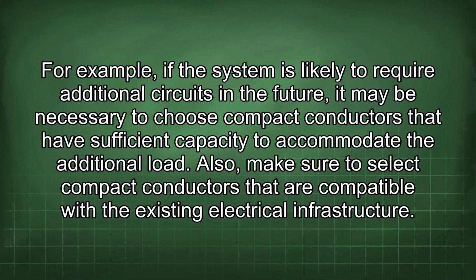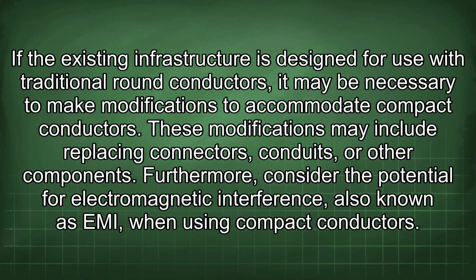Also, make sure to select compact conductors that are compatible with the existing electrical infrastructure. If the existing infrastructure is designed for use with traditional round conductors, it may be necessary to make modifications to accommodate compact conductors. These modifications may include replacing connectors, conduits, or other components.